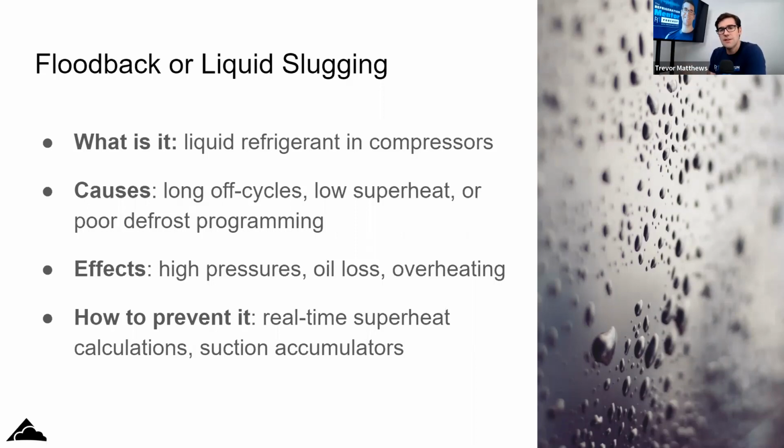So there are so many different things that you can check, because if your oil reservoir is full but it's still washing out the oil, by analytics you can tell, okay, my oil reservoir is good, I should be feeding, but now my compressor doesn't have any oil in it. The differential is too low. That's probably flood back happening. So there's lots of different analytics you can do, measuring the oil temp, measuring the discharge temp for flood back.